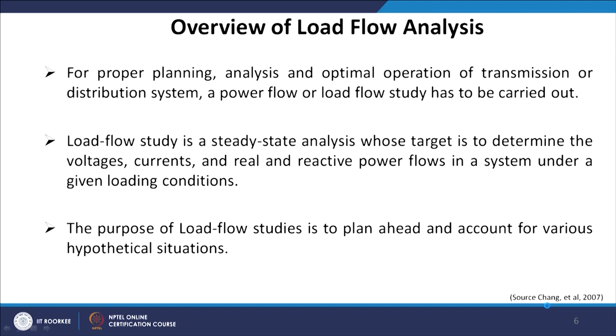Now, the purpose of load flow studies is to plan ahead and account for various hypothetical situations. If the load scenarios keep on changing, how do I plan my system so that the voltage at each and every node does not violate the permissible variation, maybe 2%, 5%, depending upon the utility? Now, there are well established algorithms: Newton-Raphson load flow, Gauss-Seidel load flow, fast decoupled, and Broyden methods.